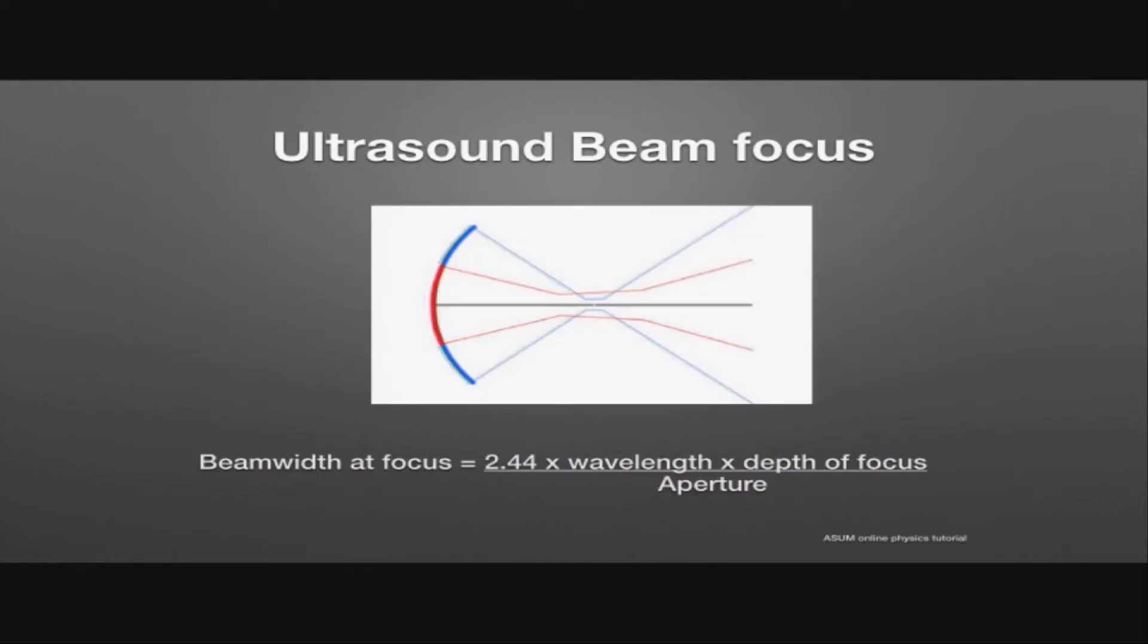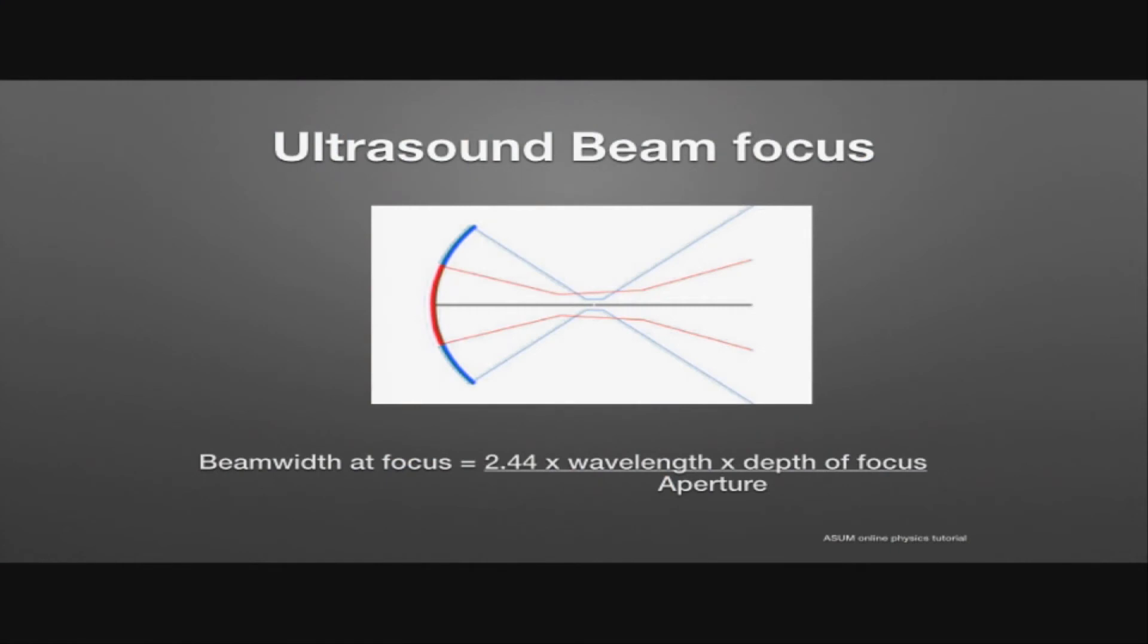Another important equation to remember is the beam width at the focus, which is equal to 2.44 times the wavelength, times the depth of focus, divided by the aperture. And again, it's probably important just to remember that the beam width at the focus is proportional both to the wavelength, the depth of the focus, and it's inversely proportional to the aperture. Another way of potentially thinking about that is the narrowest beam is achieved by the highest possible frequency.